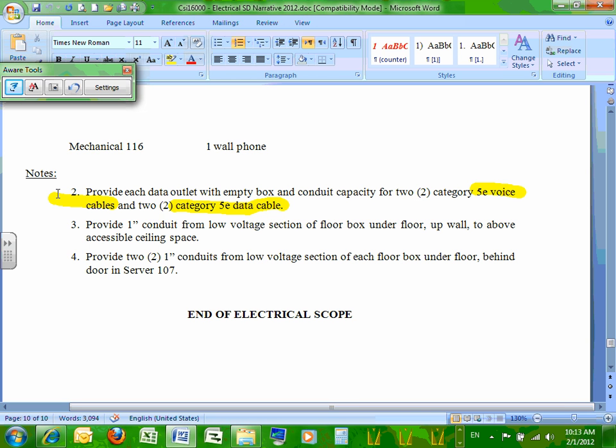A lot of these companies, and I'll always use the example of schools because I've done a million of them, hire their own. They have their own technology guy, their own IT guy, each school does, on staff. So we do a little remodel where we add 3 classrooms to a building, and they might just say, we're going to have our guy do that, and he'll get everything working and everything will work fine, but no one's inspecting his work. So you go up above the ceiling and it's just thrown above the ceiling tile.